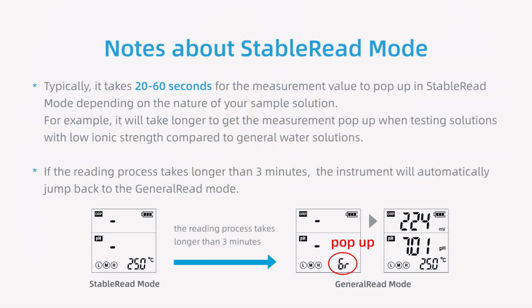Notes about stable read mode. Typically, it takes 20 to 60 seconds for the measurement value to pop up in stable read mode depending on the nature of your sample solution. For example, it will take longer to get the measurement pop up when testing solutions with low ionic strength compared to general water solutions. If the reading process takes longer than 3 minutes, the instrument will automatically jump back to the general read mode.